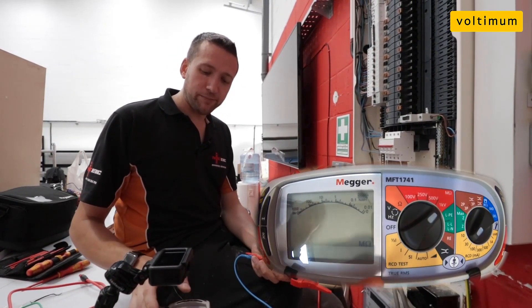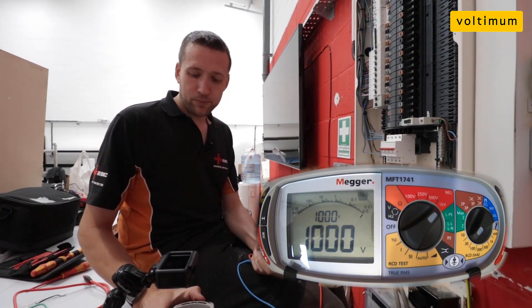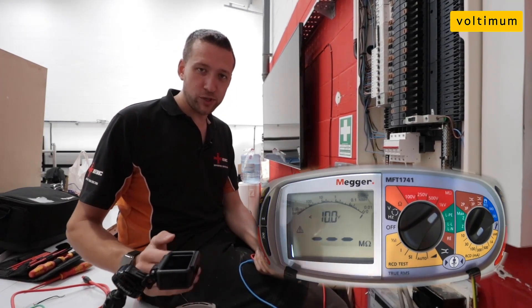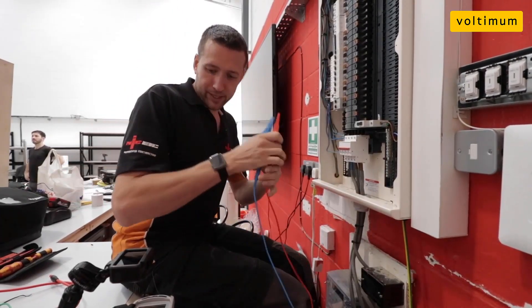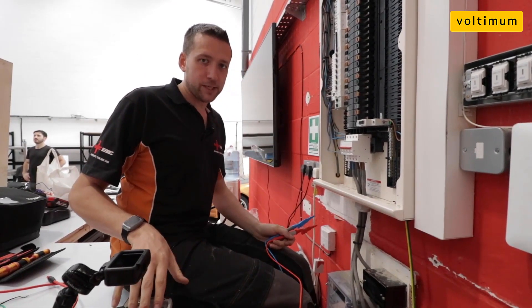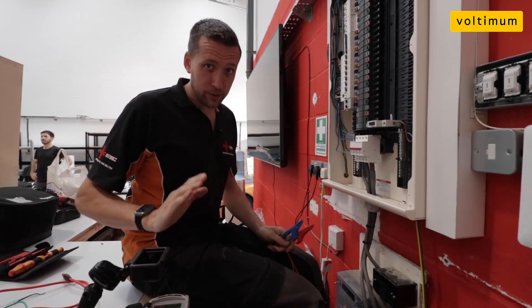On the insulation setting, when you put it to 1000 volts they've kept the little confirmation warning just before you hit test — just to give you a warning before it introduces the test voltage. I like that feature as well. Now Megger claim that this test meter isn't affected by RCD uplift, so we're going to put that to the test. They are adamant that this is the case.